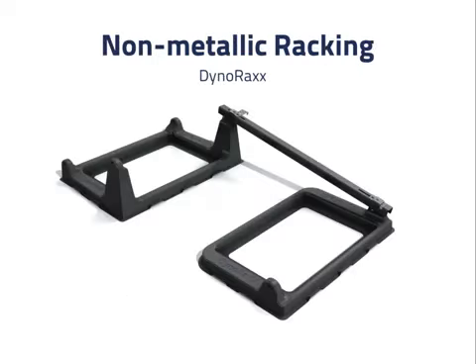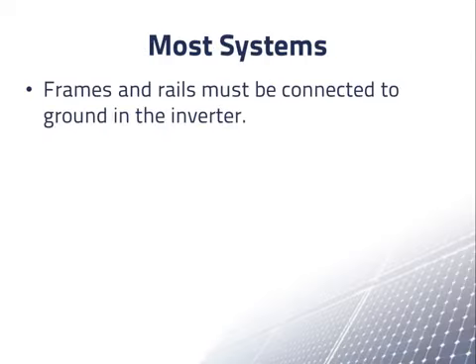Non-metallic racking has also been developed by a few manufacturers. This rack is made up of fiberglass, except for the metal clamps to hold the PV modules in place. This rack is intended for a flat roof. We are not aware of any non-metallic racking for sloped roofs, except for products which integrate solar cells into a roofing product.